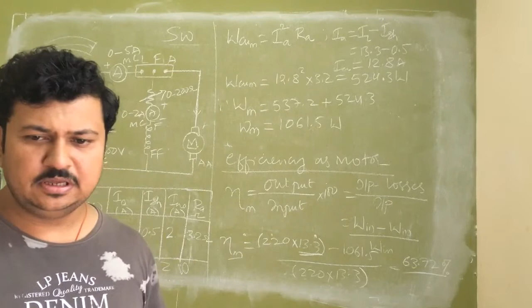So when the current drawn by the motor is 2.5 amperes, I can't say the motor is at 20% load condition because load is not connected to the motor at all. But still there is current drawn by the motor. Therefore, line current divided by 2 will not give 50% load condition. Line current multiplied by 0.8 will not give 80% load condition. So the best I can do in Swinburne's test is keep only one calculation for the motor at full load. That's it. If you divide the current by 2, by 3/4, by 1/4 and calculate the efficiency, that is not correct for the motor. Okay.